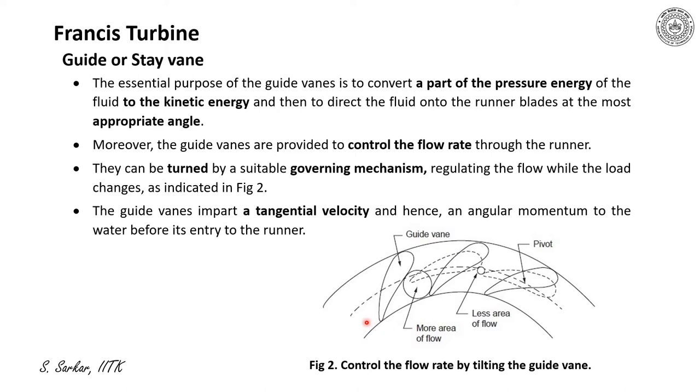Please note that for the position which has been illustrated by the dotted line, the flow area is much less and thus the flow rate. Hence, the flow rate can be controlled by turning the guide vane by a governing mechanism.